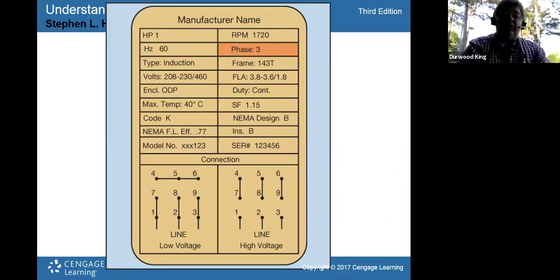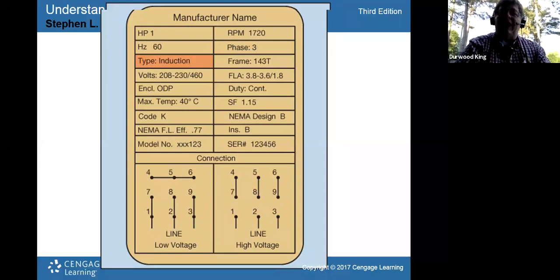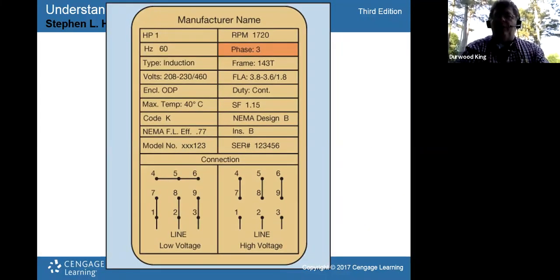Phase is going to tell you how many phases the motor has. Is it single phase, 2 phase, or 3 phase? That's how many hot wires you have. For a 3-phase motor, there are 3 hot legs, and for single phase, you can have 2 hot legs if it's single phase high voltage. So if you've got a single phase motor, in all cases, it's going to be two current carrying conductors going to the motor. If it's a single phase motor on 120, it's got a hot and a neutral that carry current to and from the motor. If the single phase motor runs on, say, 240, it's got two hots, an L1 and an L2, and they're both hot, but they're different phases. So it's still two current carriers to the motor if it's single phase.